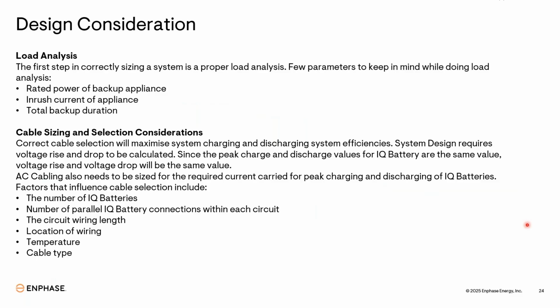See the load in that cable: the current in that phase will increase. You need to make sure the current for battery charging and the current for the load running are both taken care of, so that the cable is sufficient to bear both currents. The battery itself will draw a current of about 16.7 ampere, near 17 ampere, for charging from the grid in case PV is not there. You need to consider that current also, plus the appliances' load current. So choose your cable size accordingly.